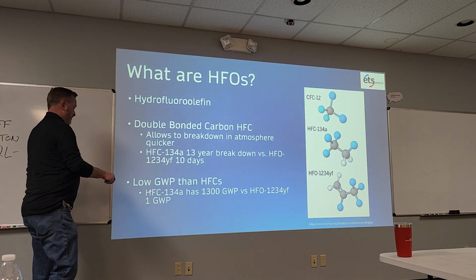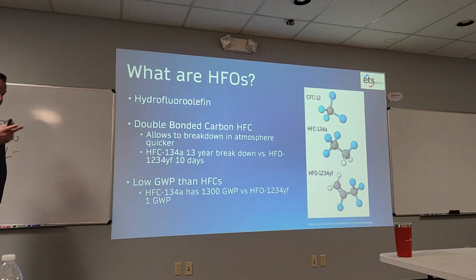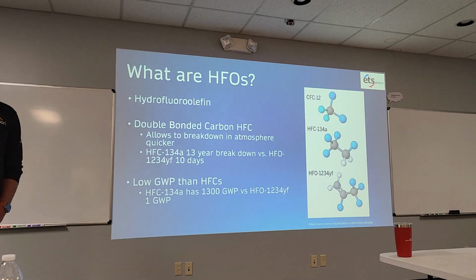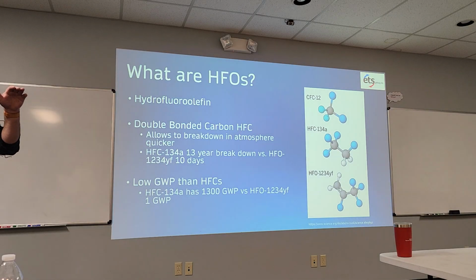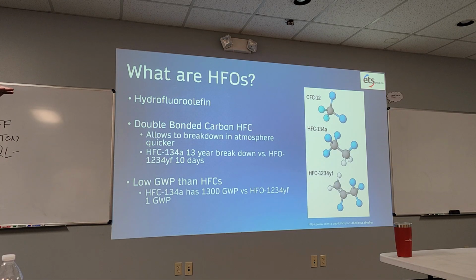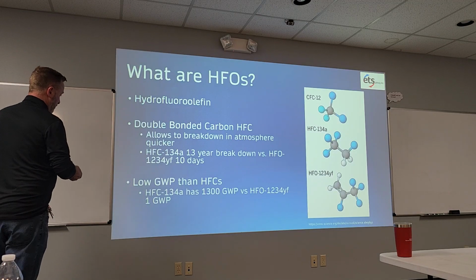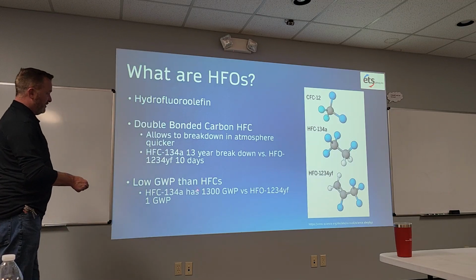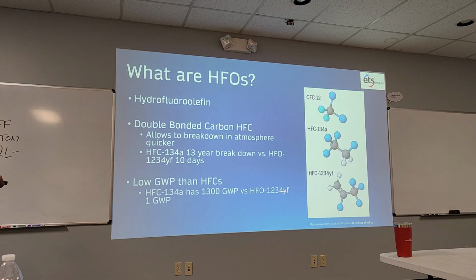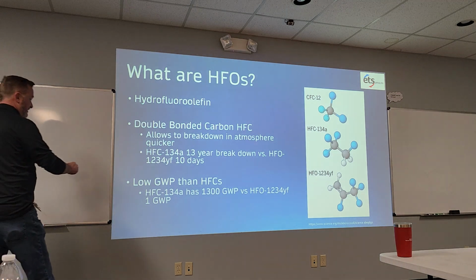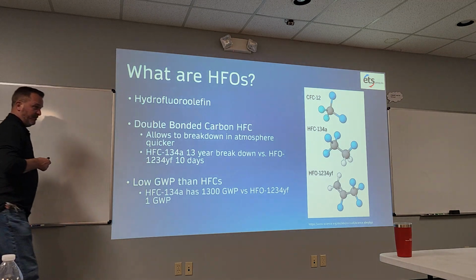The next thing is GWPs, which I'm sure you guys are familiar with. What does GWP stand for? Global warming potential, right? The lower the GWP number, the better it is for the environment. So that's what they're putting all these regulations on. They're saying you've gotta be below a certain GWP refrigerant by a certain time, okay, and we'll go over those. So 134A here has a 1300 GWP versus 1234YF, which is 1. Right, kind of where you get the whole 13 years versus 10 days. So that's the drive right here, is that GWP number, okay?